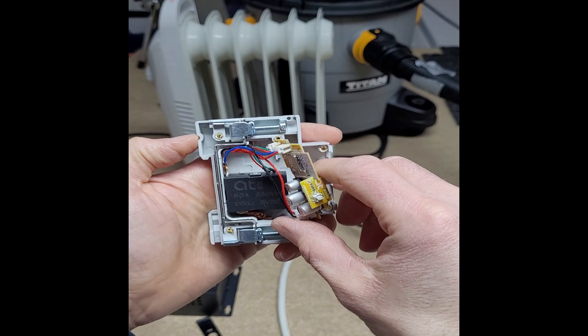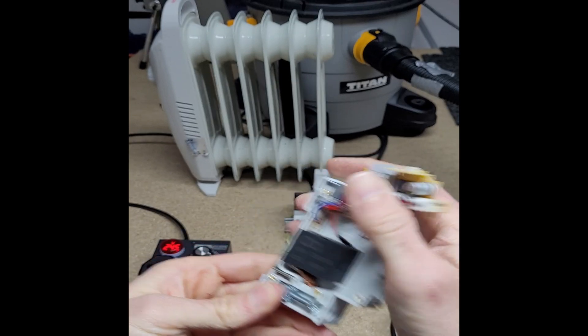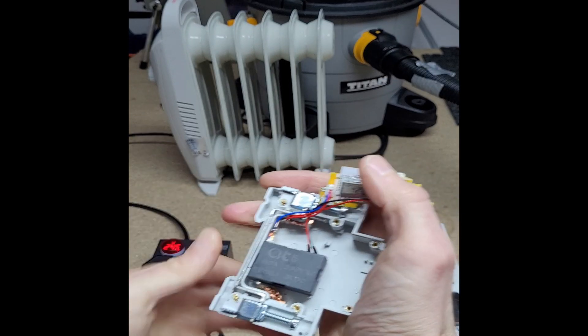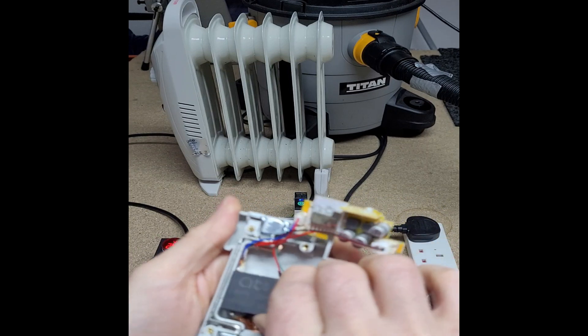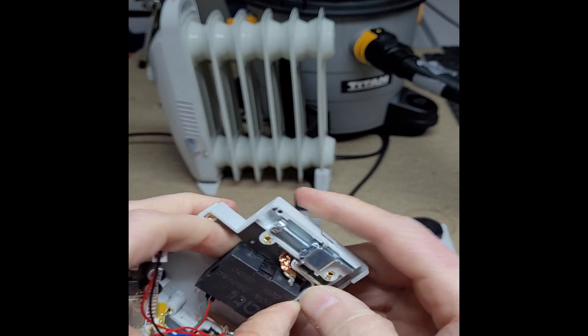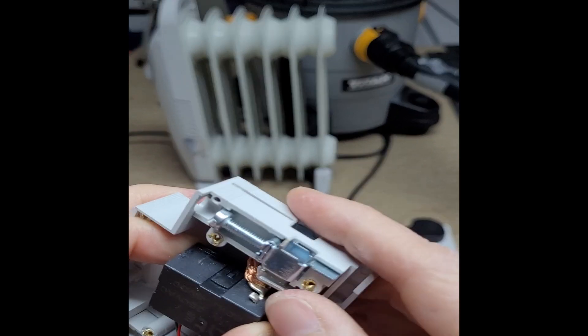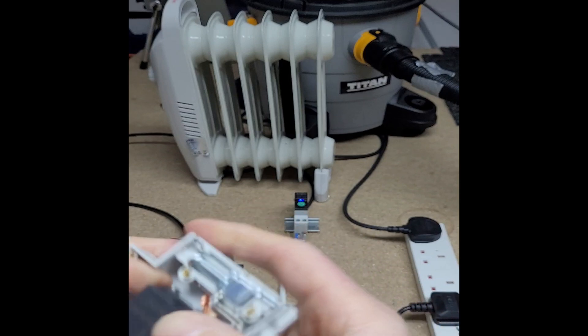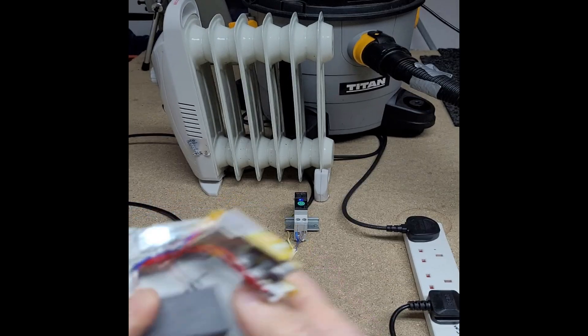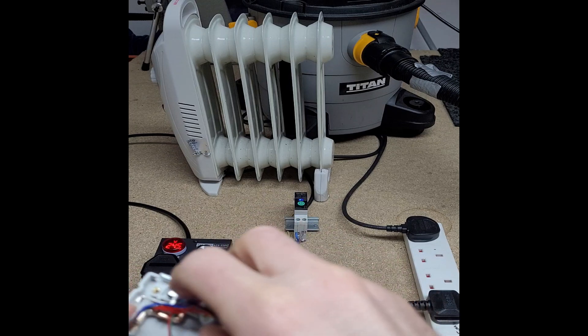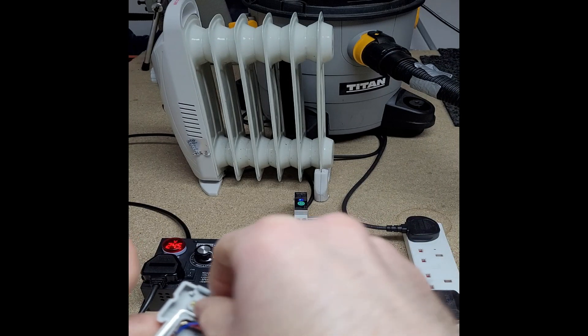Obviously these are somewhat safety critical, so you want to have a look inside it or at least know what's inside. I've destroyed this one - this is a six amp one but they're the same inside. What is good about this, it's got that big 60 amp relay. I wouldn't go setting it to 63 amps and assuming it's going to cope with that. It's got a nice big solid piece of copper wire going to the terminal between the relay. What's good about it - it's not soldered, it's welded, which is pretty good. Likewise, that's welded on the other contact too, and these wires that go off to sense the currents and power this little board, they're welded as well.